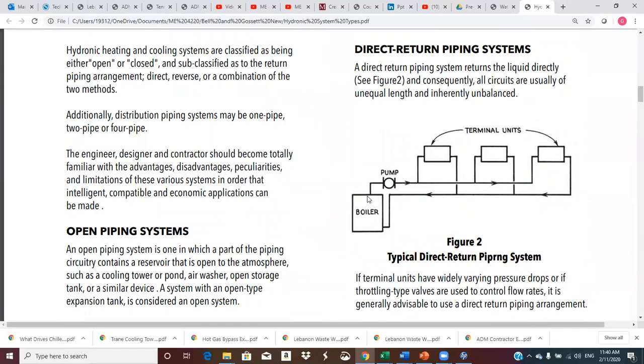So anyway, we pull hot water out of the boiler, we pump it up to this point, and we come out here and we branch up to the coil on some sort of a terminal. This could be a radiator, or it could be a hot water coil in an air handling unit. We come back out of that, we go down to the return, and then we go right back to the boiler. So you see, this is called direct return because this closest unit has the shortest supply piping.